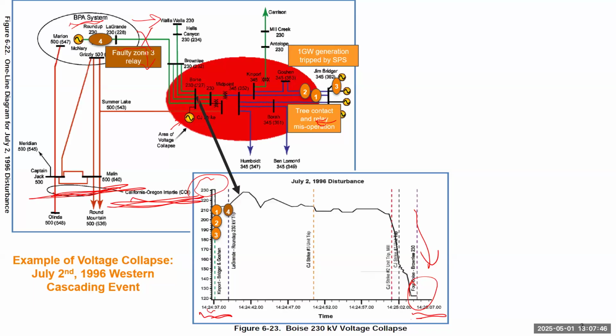All that happened in several seconds. The next event made this generator overloaded, so that generator tripped. And there's another line that is overloaded, which became another zone 3 relay trip. So after the 7th or 8th event happened, the voltage quickly dropped to a very low value. Here it is about 120 kV. The voltage suddenly dropped to about 50 to 60% of the normal voltage. Then the voltage collapse happened.